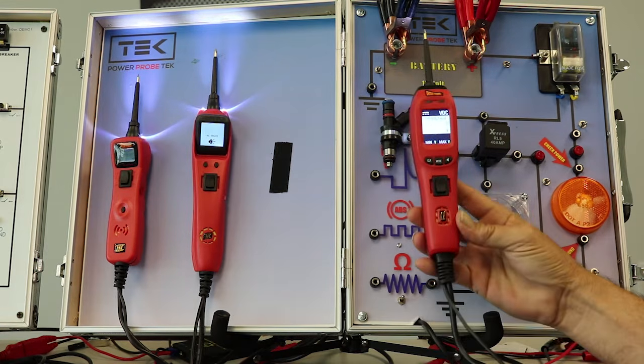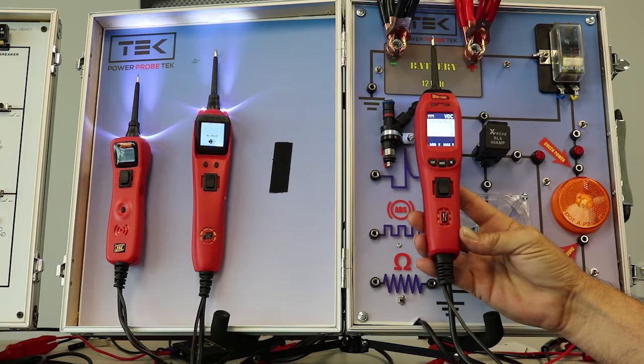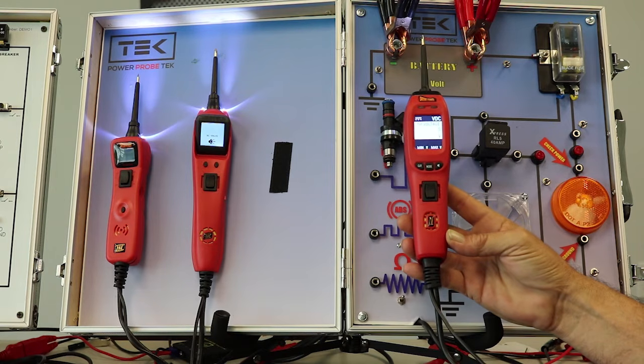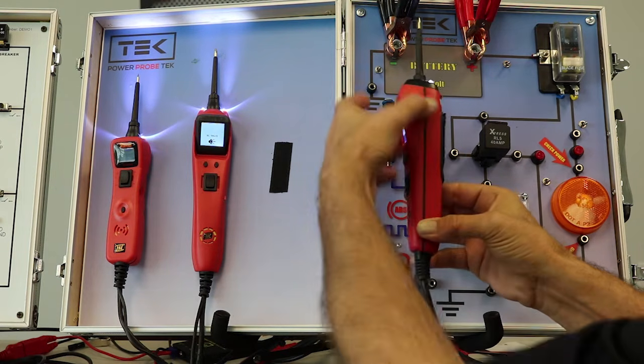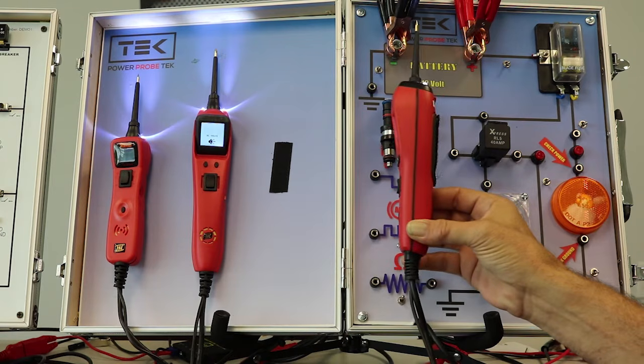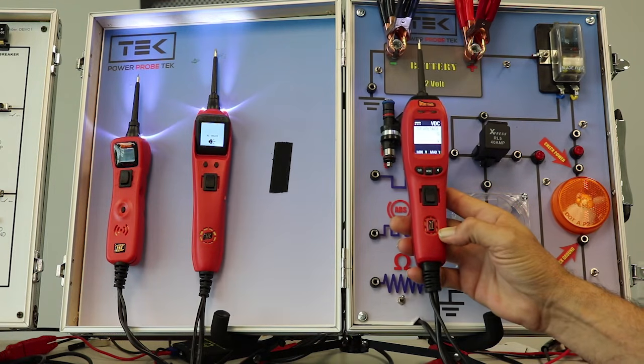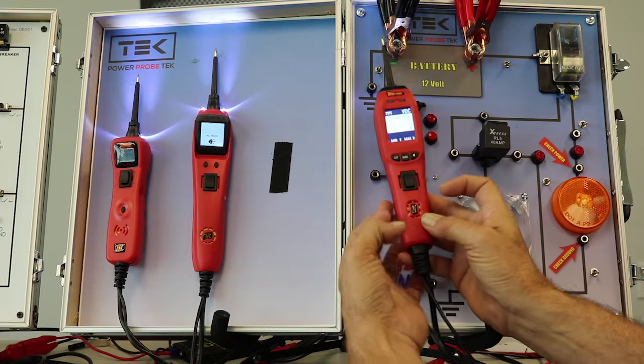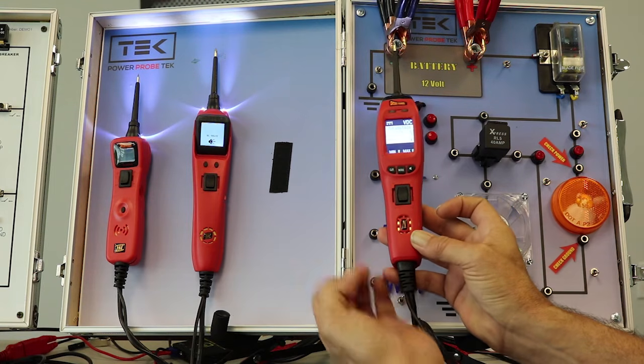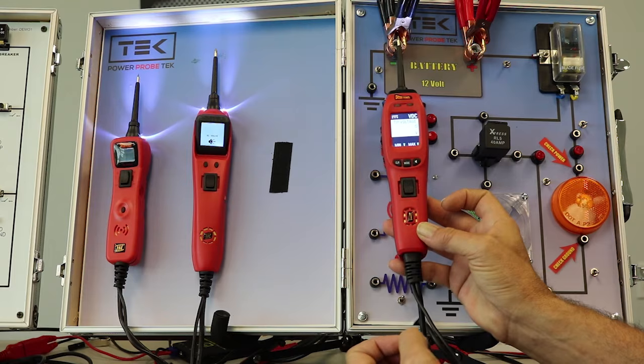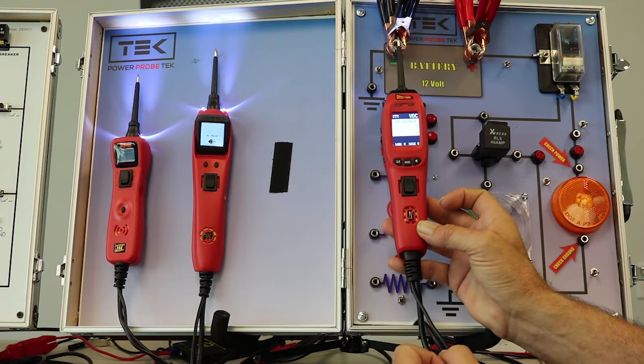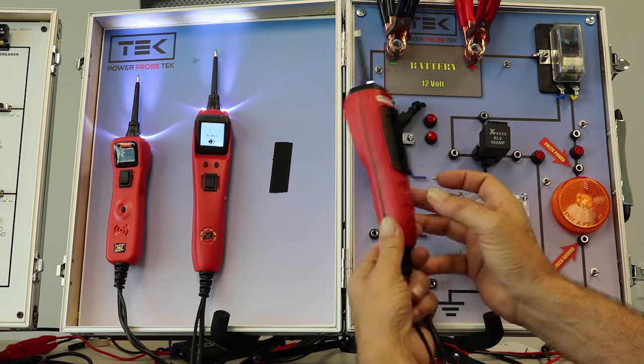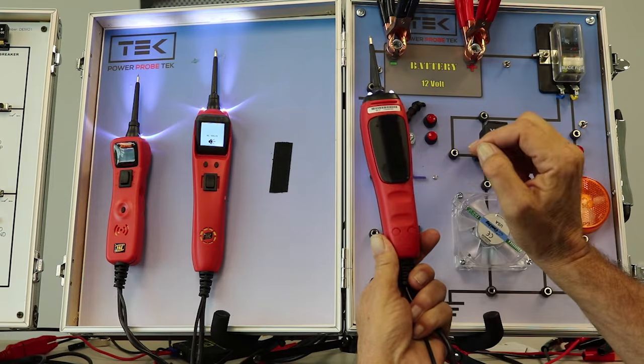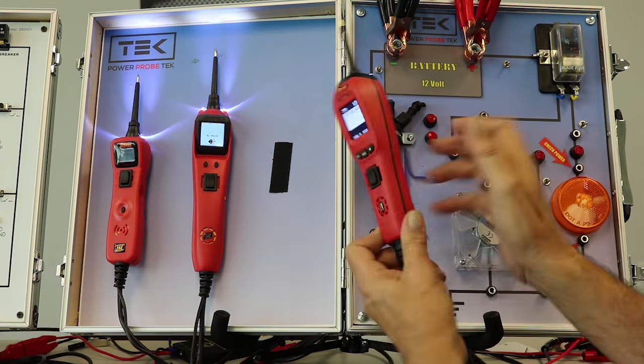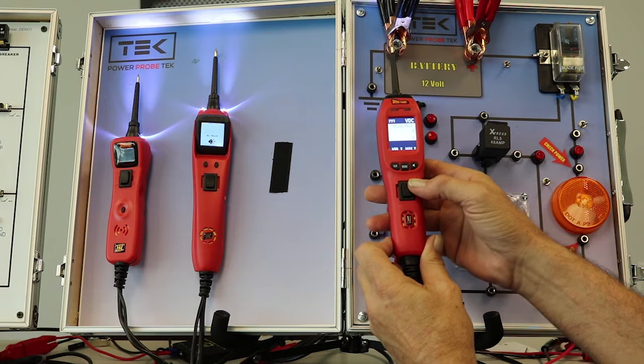A couple of less obvious things on the Power Probe 4 that are improved over the Power Probe 3: it now has a sealed housing, so much more weather and watertight. All the tools still have the easily replaceable rocker switch that pops right out of the front and can be replaced if worn over time. The Power Probe 4 also has a replaceable circuit breaker under this back panel, so long life, easily serviced parts if they do wear out.